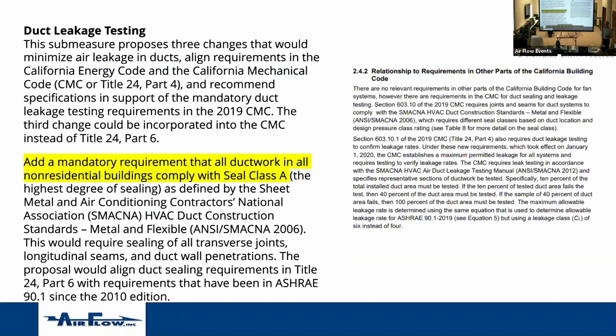Different stuff in California. California requires everything to be seal class A. I'm going to tell you a lot about what seal class is. It means basically everything in California is made like it's high pressure ductwork, or it's sealed like it's high pressure ductwork. Why? Because California is way more stringent about energy codes than anywhere else. And as we're starting to see with electrification, those things tend to move from the coasts inward. So maybe this is on a radar. And I would say this is actually really good legislation. Duct leakage, we'll get to the end, but it can be a big deal.